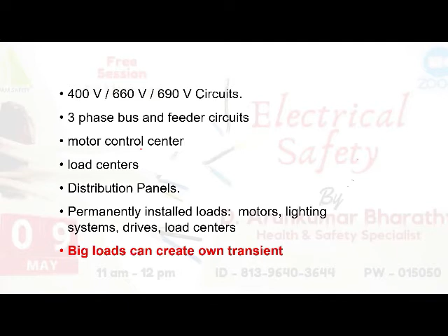This is the list: 400, 660, 690 volts, because industries use a lot of different voltages. This is location 3, meaning all 3-phase bus bars, feeders, motor control centers, load centers, distribution panels, permanently installed loads, motors, lighting like halogen and mercury lamps, and whatever big machineries you use in production. These are considered location 3, meaning a power circuit measurement.